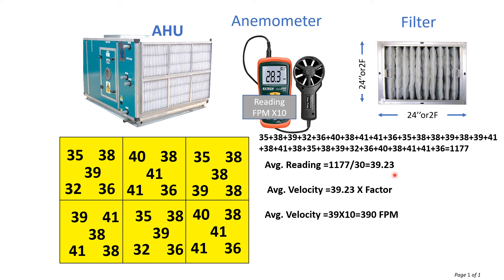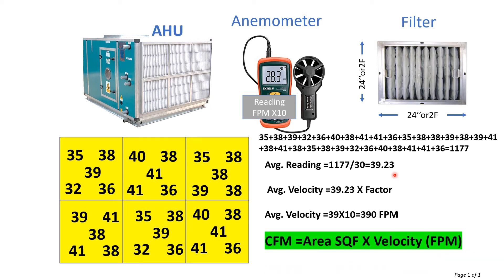The average velocity is 390 feet per minute, and what we need to calculate is CFM — cubic feet per minute. This FPM value we need to multiply by the total area of the AHU suction side. To calculate the area of the suction side, we calculate the area of one filter and then multiply it by the number of filters. Here we have a 2-foot by 2-foot filter, so the area is 2 × 2 = 4 square feet, and 4 square feet × 6 filters gives the total area of the suction side.